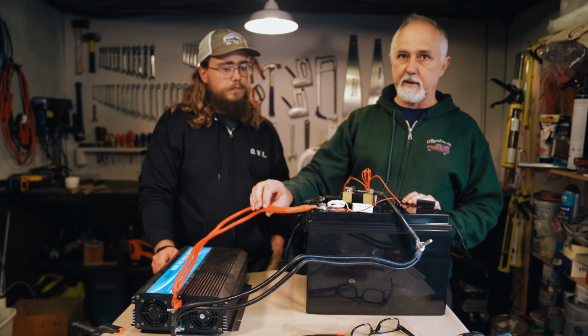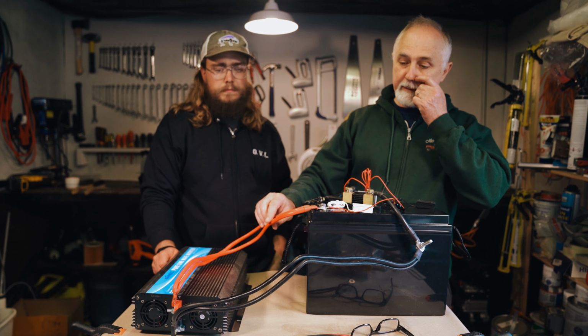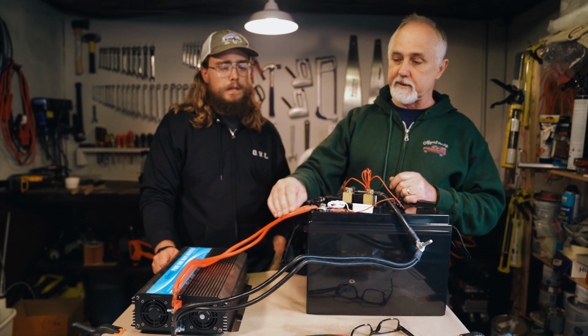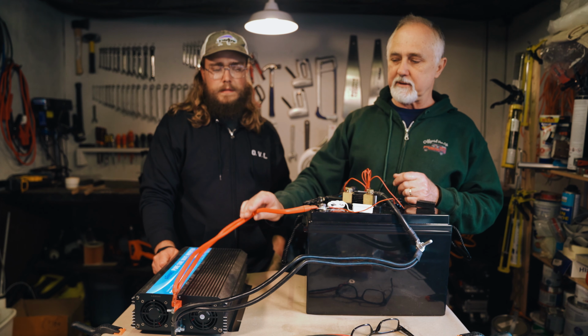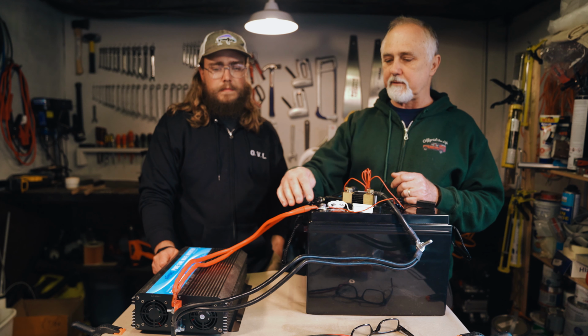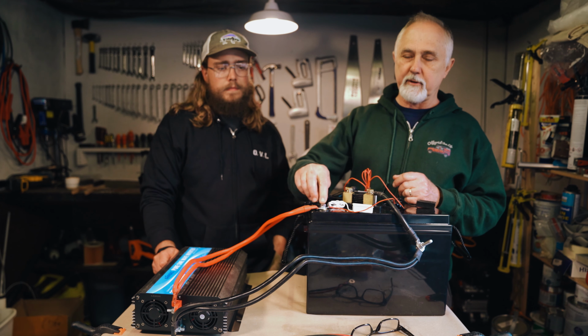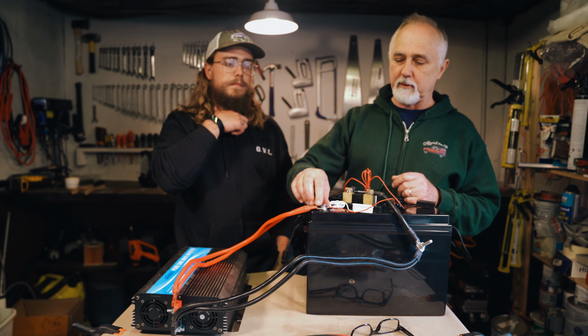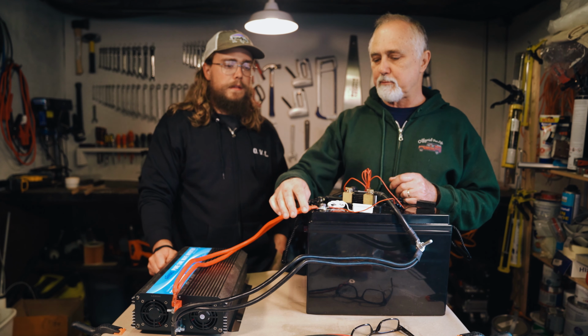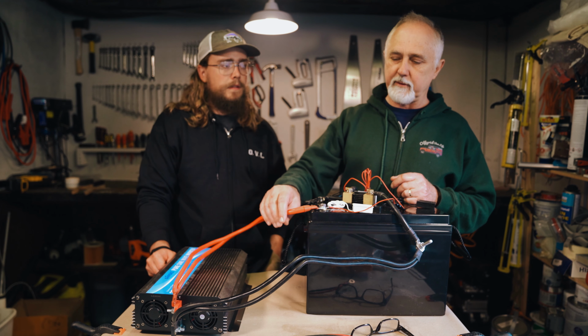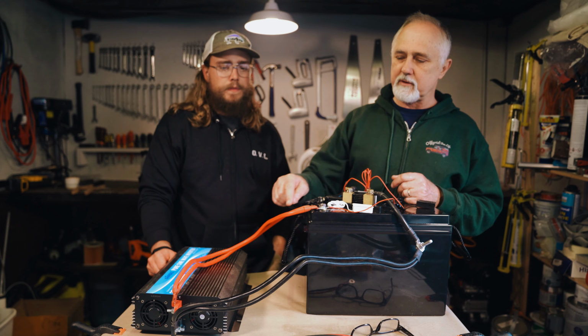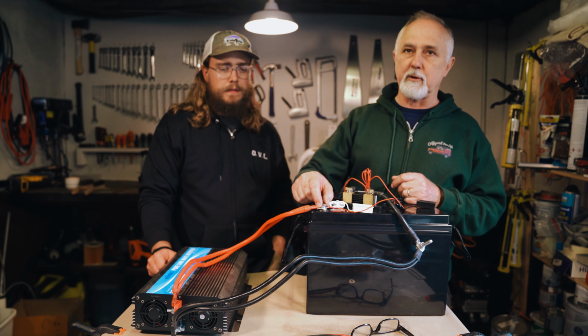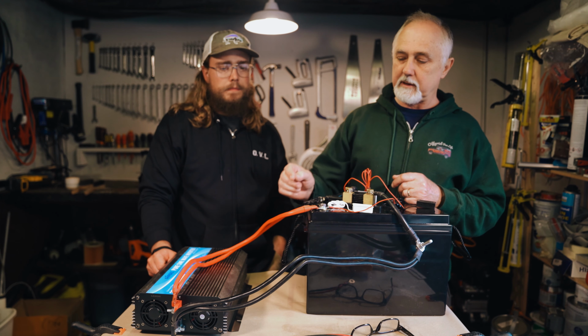These cables got pretty hot, up to about 60 degrees. They're rated at 200 degrees, so not a problem, but it got to the point you couldn't keep your finger on the terminal, too hot. That's partly because it's a very big lug on this cable - normally we change these to 35mm cables with 6mm lugs, which generates less heat.